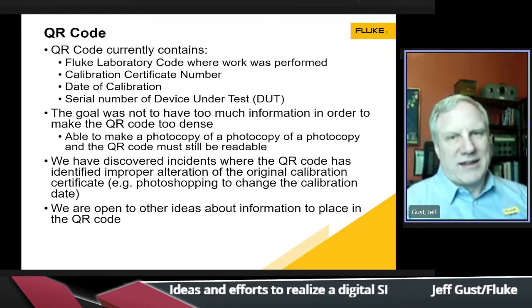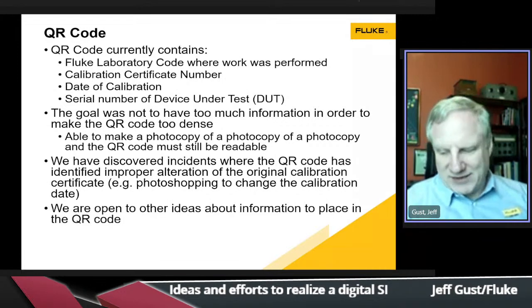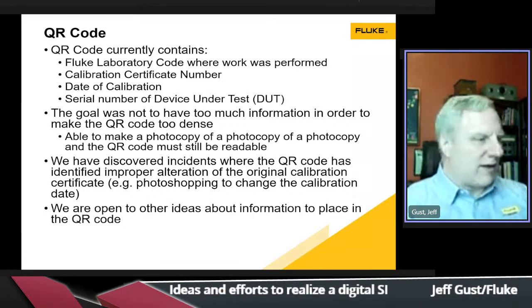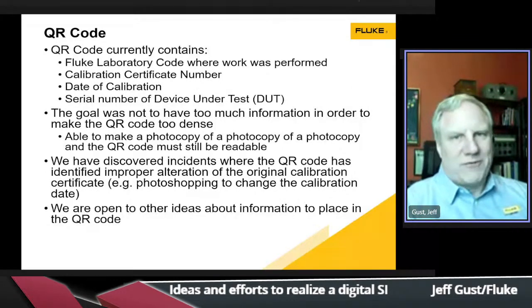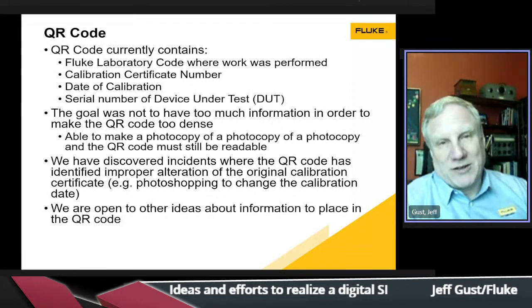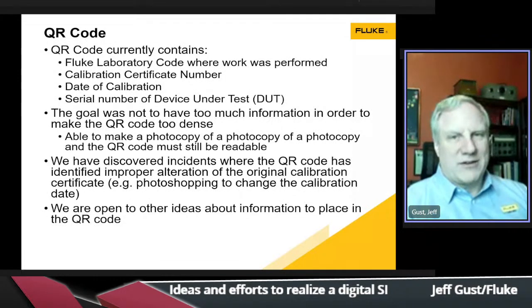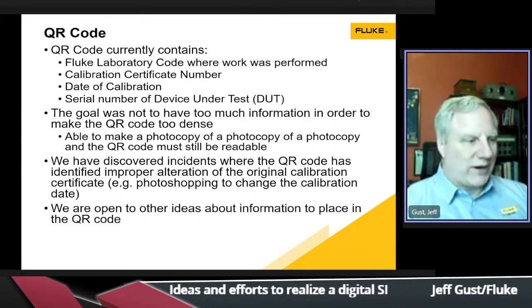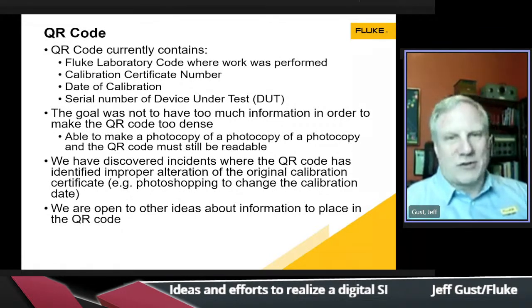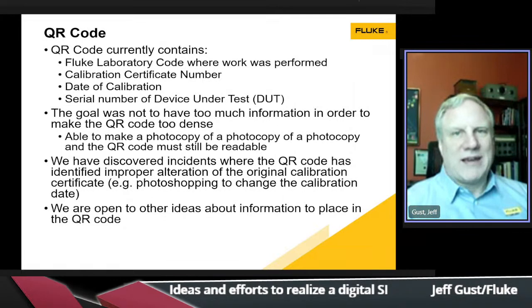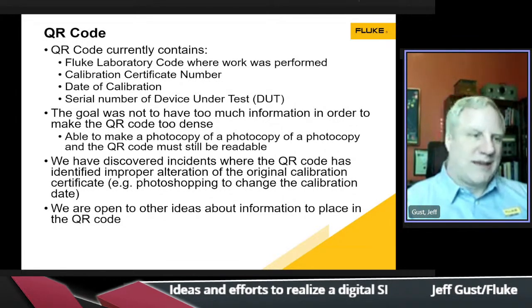I will say, again, it's not perfect security, as I believe Jean had mentioned, that yes, you can still falsify QR codes, but we found that it's a little bit better security than what was out there now. We actually discovered a couple of incidents where the QR code helped us to identify an improper alteration to an original calibration certificate. In other words, we found somebody who was photoshopping the date on their calibration certificate, but it didn't match the date on the QR code because they hadn't considered that.